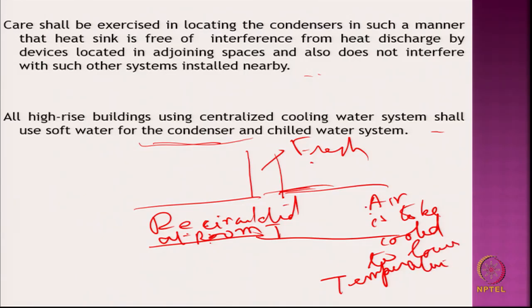So, if I increase this fresh air intake, that means outside air temperature might be 30 or 35 degrees centigrade or 40 degrees centigrade. This air might be at 25 degrees centigrade. So, following the law of mixture, this air temperature will be somewhere in between, say 40 and 25, right. Now, I have to cool it to a lower temperature than room temperature. As it enters the room, it will absorb the heat.